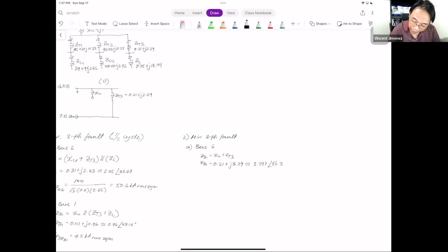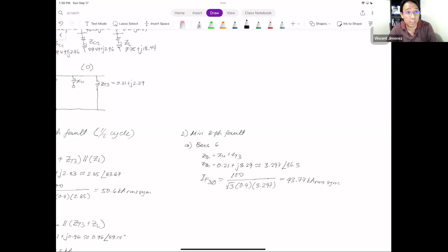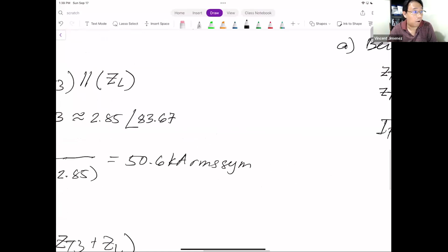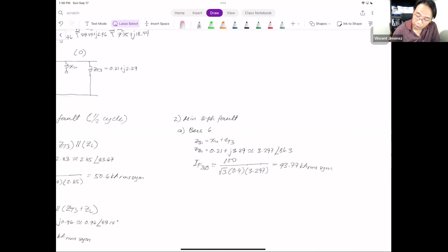Solving for the minimum three-phase IF at bus 6, this is equal to 150 MVA, consistent, over square root of 3 times line voltage 0.4 and the calculated magnitude of 3.297 per unit. We have 43.77 kA RMS symmetrical. This is not the current you will use in coordinating or setting the protective device. This current is used for selecting the kA rating. For setting, your next speaker will explain that further.